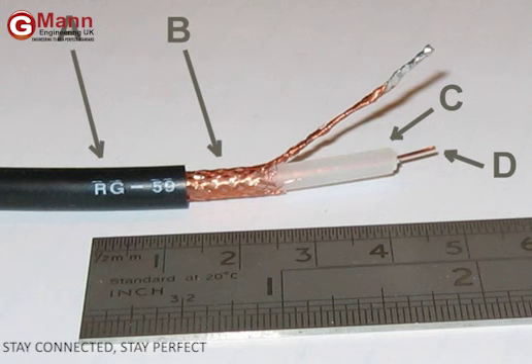For better shield performance, some cables have a double-layer shield. The shield might be just 2 braids, but it is more common now to have a thin foil shield covered by a wire braid. Some cables may invest in more than 2 shield layers, such as quad shield, which uses 4 alternating layers of foil and braid. Other shield designs sacrifice flexibility for better performance.